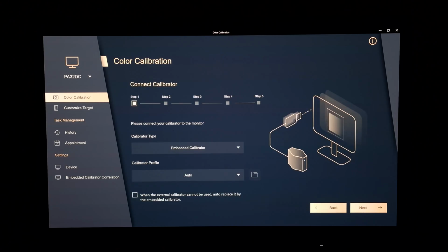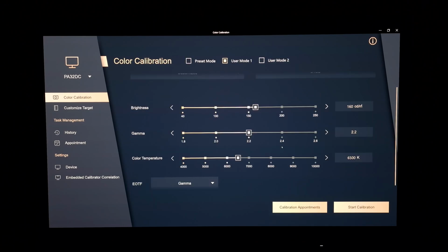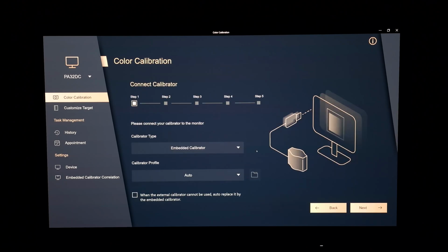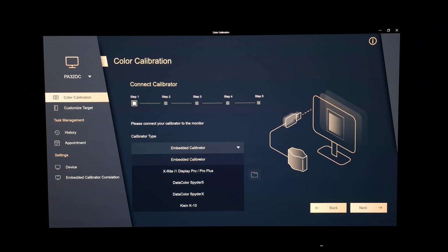So if you want, you can have the monitor calibrate, so it's using the settings you just selected. This would be overwriting user mode 1 with these specific targets. And you can choose the calibrator you want to use.